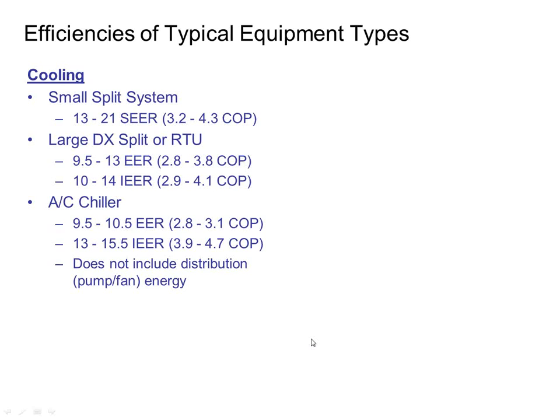COP is coefficient of performance. How much electricity and fuel sources did I buy versus how much did I get out. So how much energy did I bring into the piece of equipment, how much capacity did I get out of that piece of equipment. It's a direct ratio. So for every 1 kilowatt hour I buy from the electric utility, I'm getting 3 units of equivalent energy out of it. It's 320% efficient to 430% efficient.